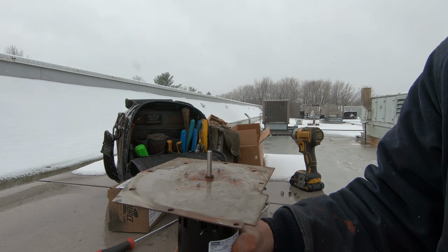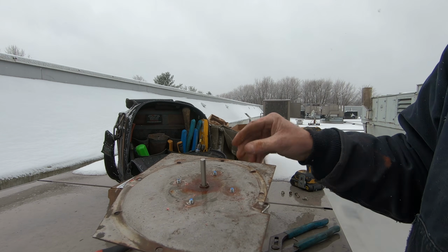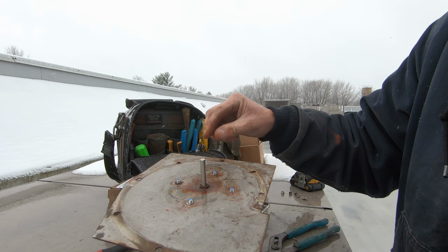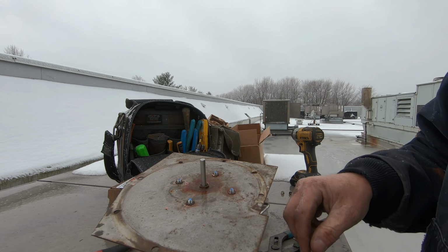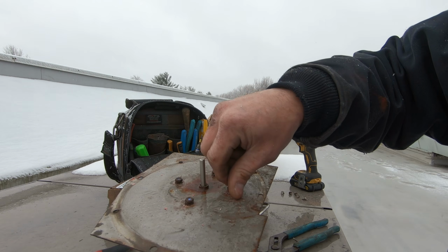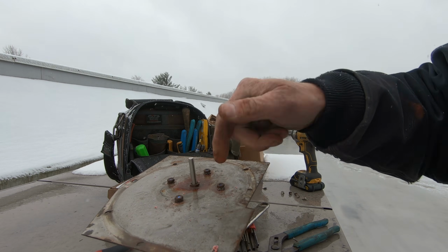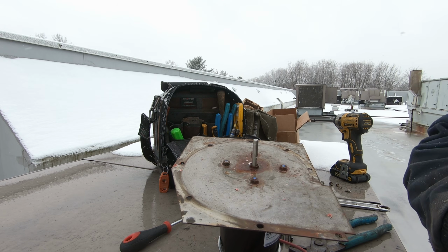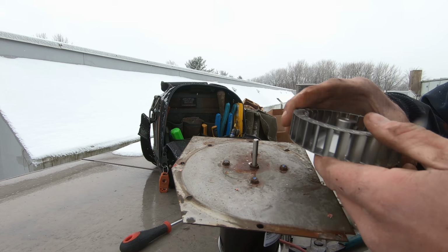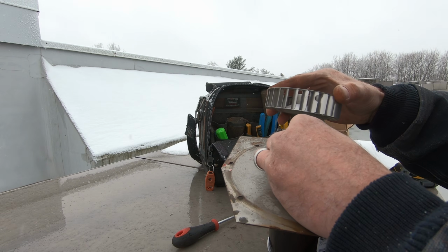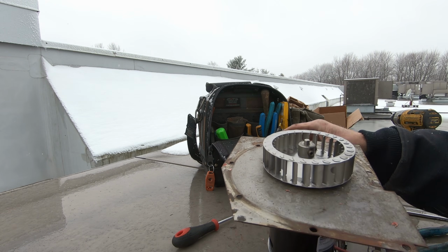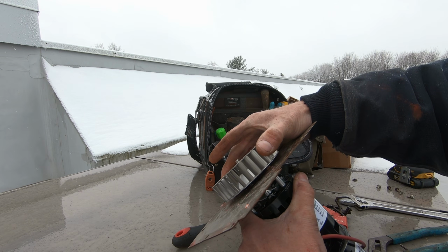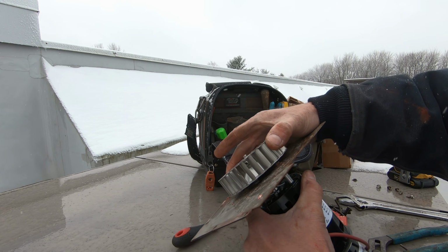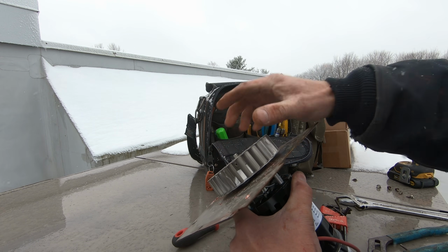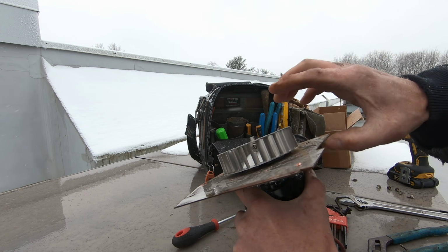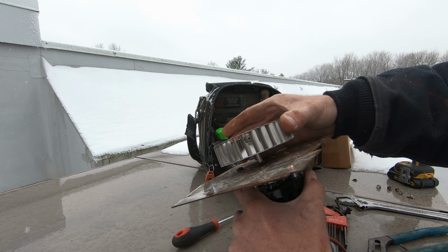Just like that. Now that we've got that in place, go ahead and put on all your lock washers and then your nuts, and tighten everything down. Get your squirrel cage out, make sure it's the right direction. So we've got the right blower wheel here. Let's place it on there, and then what I normally do is just lift it up slightly above the top of those studs there, because you're gonna have another plate here and you don't want the blower wheel way up high.